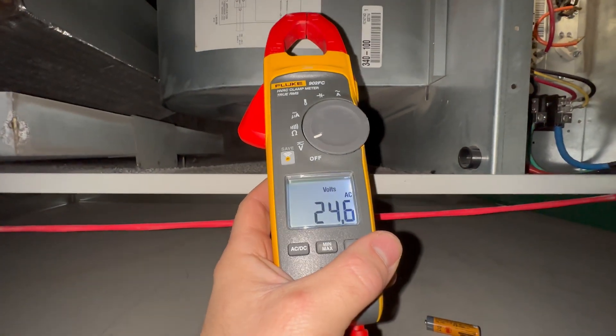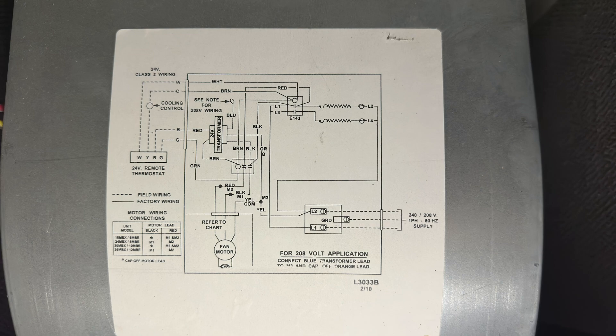But you have to be patient when troubleshooting sequencers. Wait at least two minutes because there are delays on these. That's why they're called sequencers. After two minutes though, nothing came on.